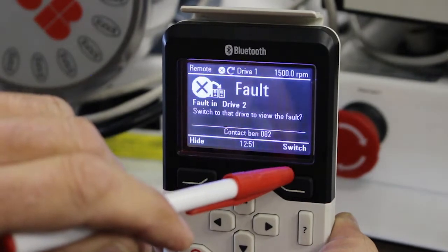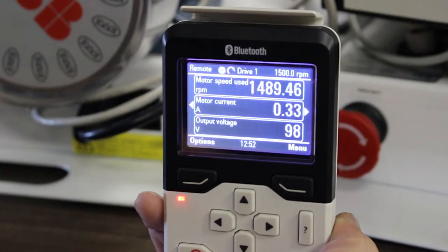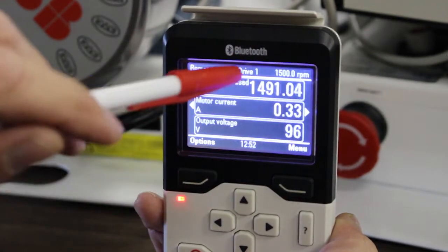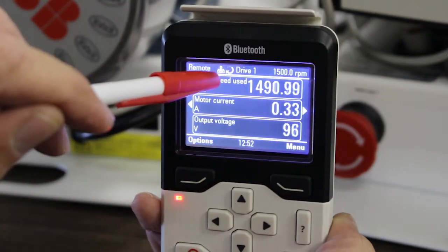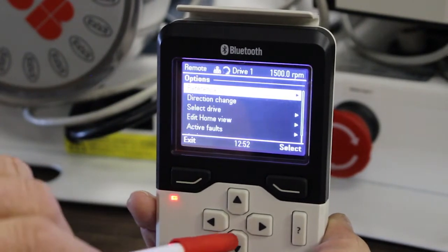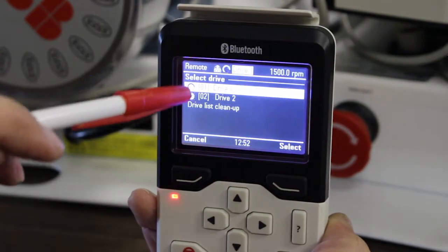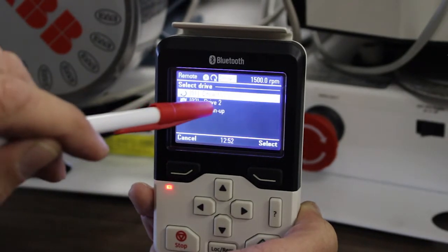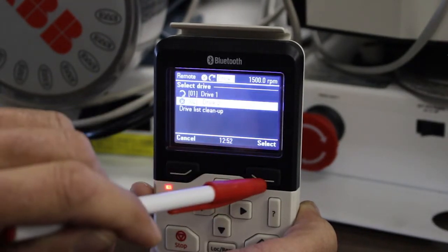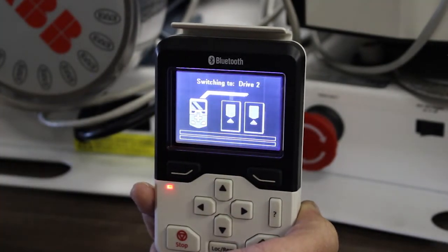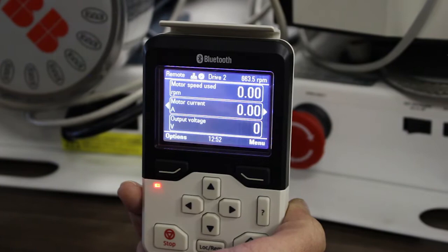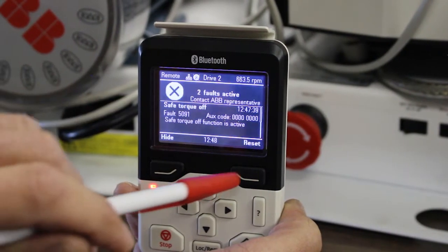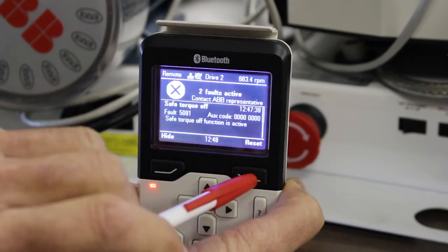I can either switch to the faulted drive from here, or say your colleague just hid the fault. I see Drive 1 running with a fault on the network icon. I go to Options, Select Drive — it shows Drive 1 is still running and there's a fault in Drive 2. I scroll to Drive 2, say Select, and it goes over to Drive 2. It now shows the active fault and I can fix and reset it as normal.